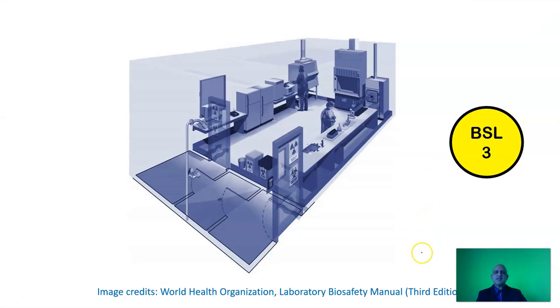A biosafety level 3 laboratory or BSL-3 has additional components which one must incorporate into the design. The first aspect is the door. This door is equipped with requisite signage as in a BSL-2. However, there is additional security precaution in the form of a keypad or an identification device.